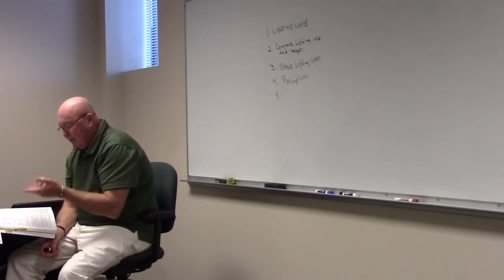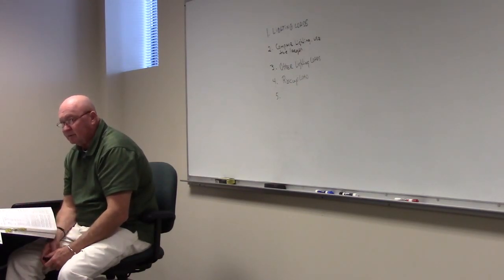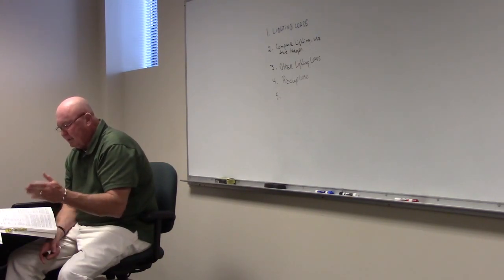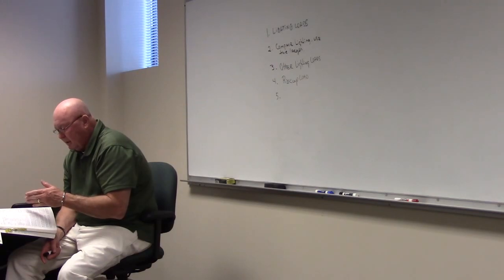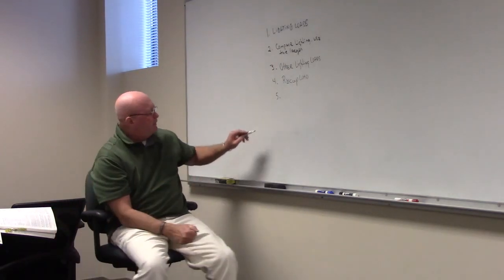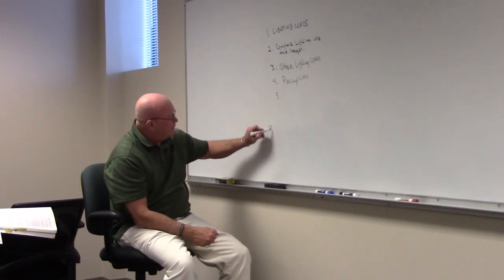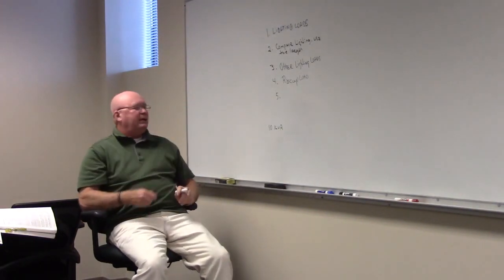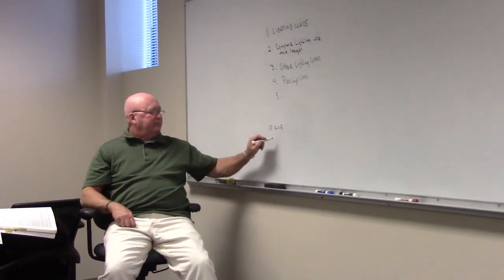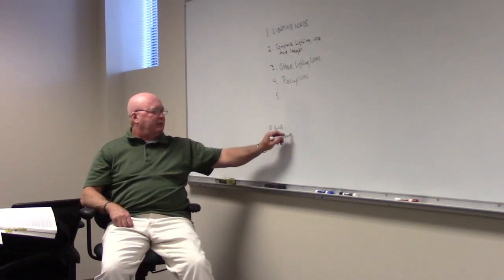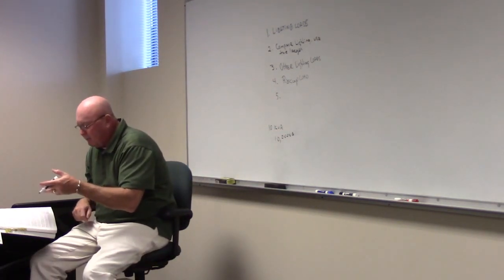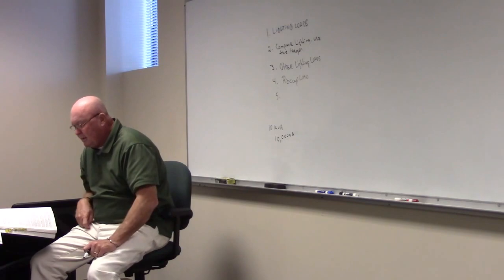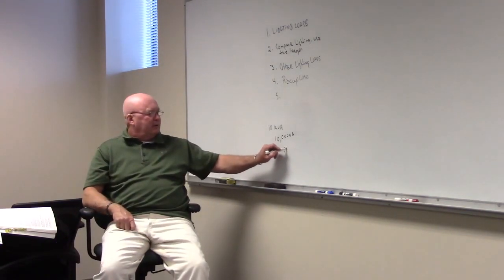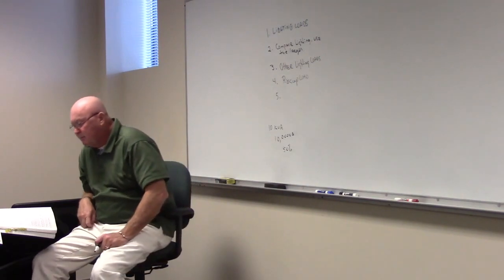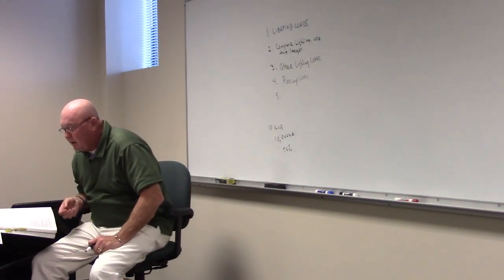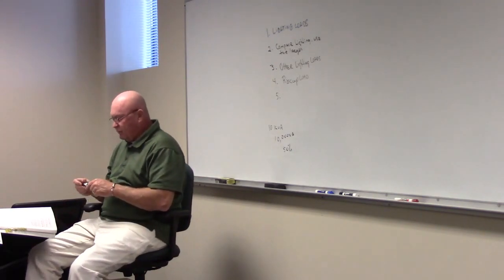220.44, demand factors for dwelling receptacles. There's a table there. So the first 10 kVA, okay? Now what's 10 kVA? Let's talk about this and make sure we understand this. 10 kVA is how many volt amps? 10,000. 10,000 volt amps. So for the first 10,000 volt amps, we're going to do 100%. And then everything over, we're going to do what? 50%. Big difference.